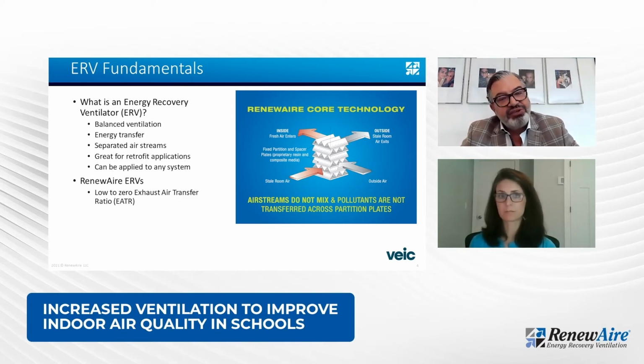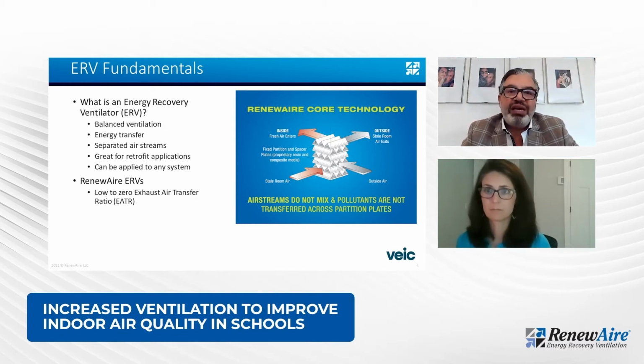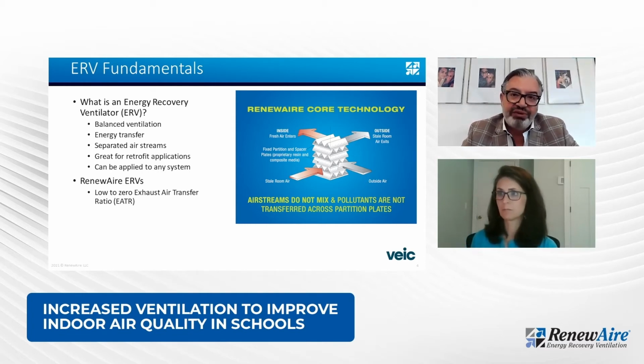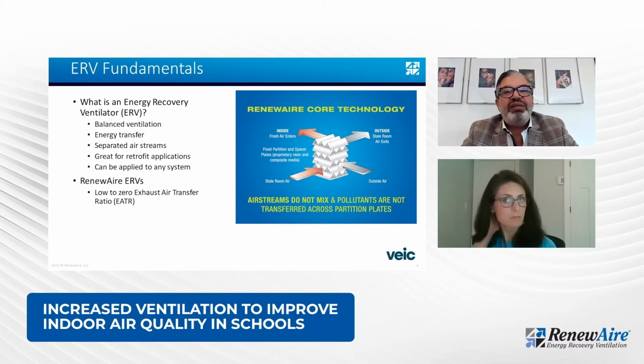Now, this is what becomes interesting. There are products called HRVs, which are heat recovery ventilators, that only transfer sensible energy. What we're talking about is energy recovery ventilators, which is a total energy, and you transfer both the sensible energy and the latent energy. So that is the cooling or the heating that occurs, simultaneously transferring moisture.